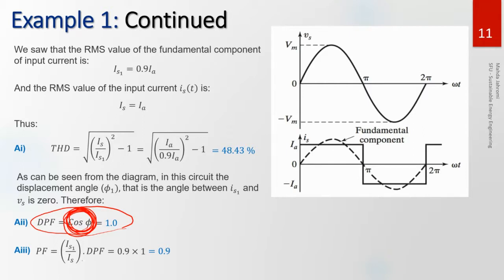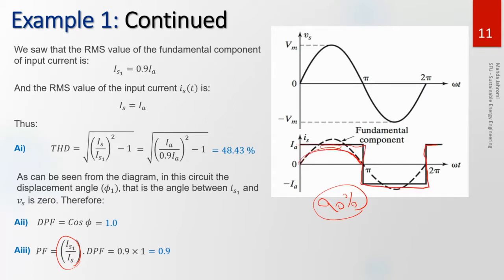For the power factor, you have to include the harmonic in it, and something that represents the harmonic contamination, which in this case is IS1 over IS. This shows how much of the waveform is actually in the first harmonic. This tells me that 90% of this square wave is created just by the first harmonic. That means that when you add all the other frequencies, you are only adding another 10% to it. Okay, so the displacement power factor is 1, the power factor is 0.9.